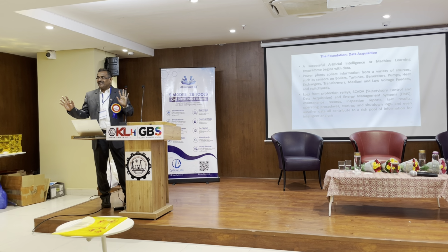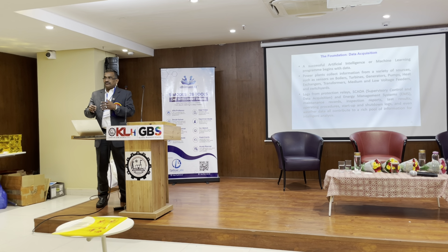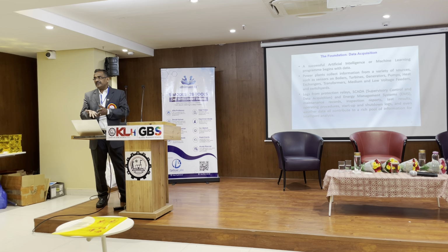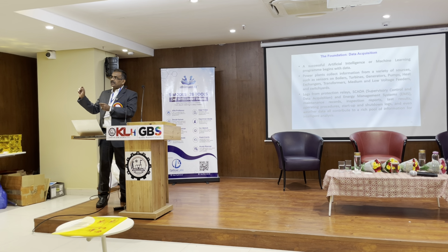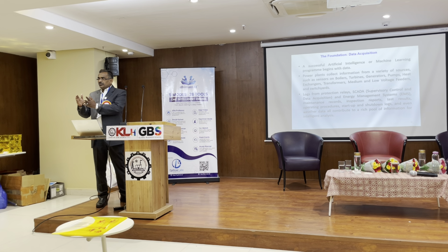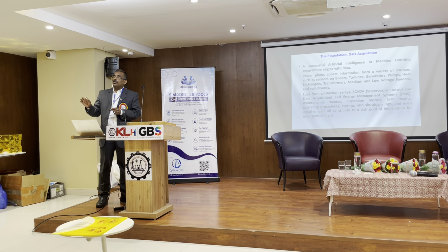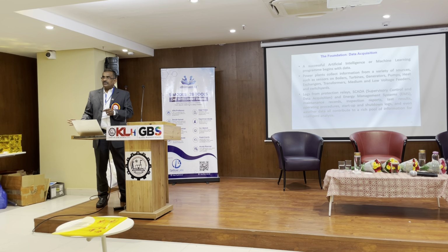Now this is the foundation — we need data. How do you generate data? We always keep sensors to monitor, say for a bearing, its temperature. The safe limit is that it should not go beyond around 120 degrees centigrade. We keep sensors continuously monitoring it. If the temperature reaches say 90 degrees centigrade, it immediately gives us an alarm, and we attend to it to see what is going wrong. If it reaches 120, it automatically trips. These safety protections have already been applied.